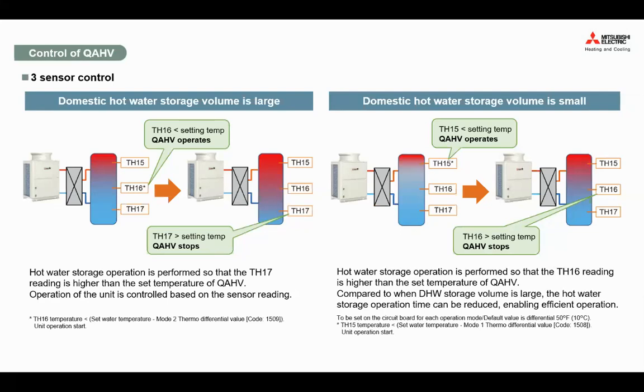So based on stratification, the coldest water is at the bottom, which is also mixed with city water a lot of the time, so you will be able to turn on and off based on that requirement. Or if the middle of the tank is too cold, then you just want to have proper mixing inside your tank, and then create hot water for your system. And if your domestic hot water storage is very, very small, then your stratification may not be significant.